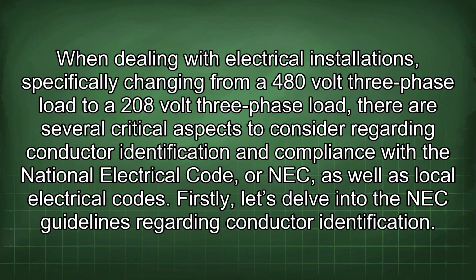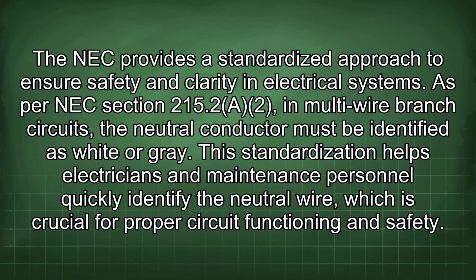When dealing with electrical installations, specifically changing from a 480-volt three-phase load to a 208-volt three-phase load, there are several critical aspects to consider regarding conductor identification and compliance with the National Electrical Code, or NEC, as well as local electrical codes. Firstly, let's delve into the NEC guidelines regarding conductor identification. The NEC provides a standardized approach to ensure safety and clarity in electrical systems. As per NEC Section 215.2(A)(2), in multi-wire branch circuits, the neutral conductor must be identified as white or gray.